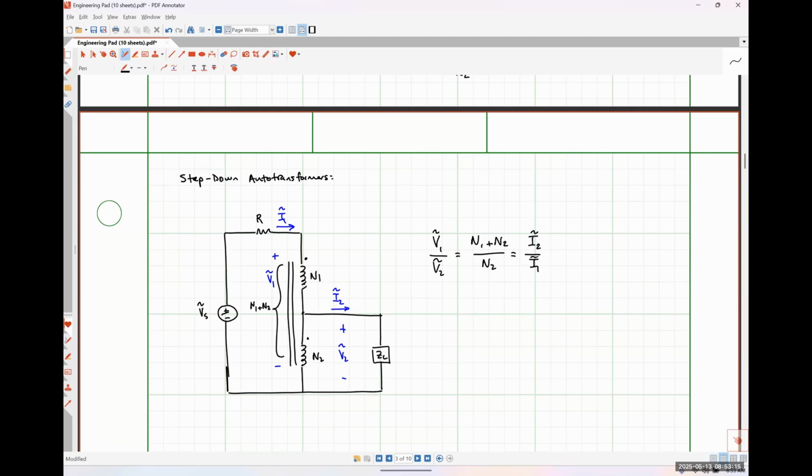So you'll see auto transformers a whole heck of a lot in the transmission side of electrical power distribution systems just because you usually don't have huge amounts of stepping up or stepping down voltages in those particular areas. You'll also see it where you need a good level of voltage regulation or efficiency as well, because they are inherently more efficient than a conventional two-winding transformer.